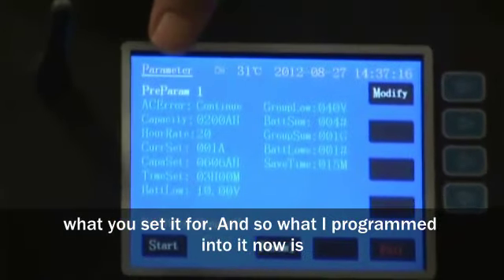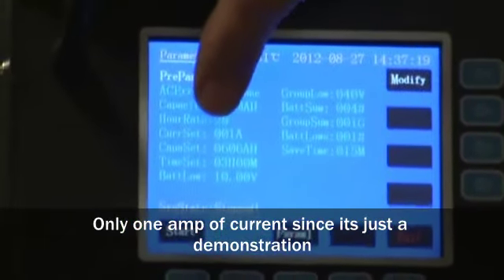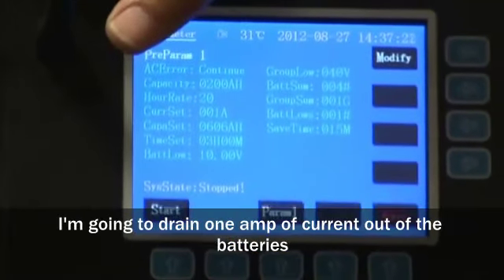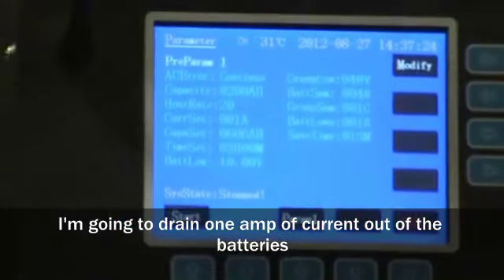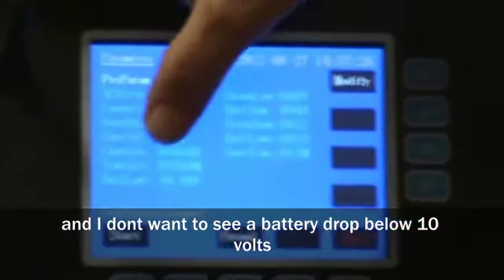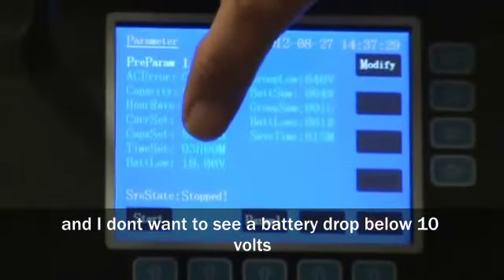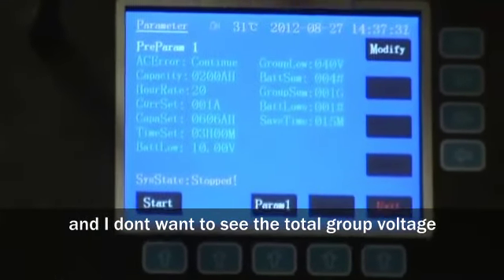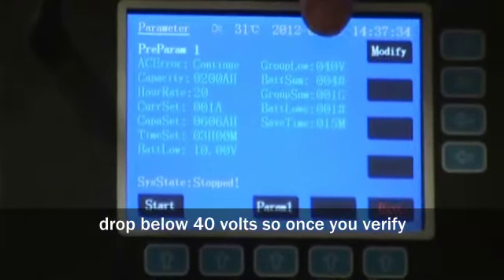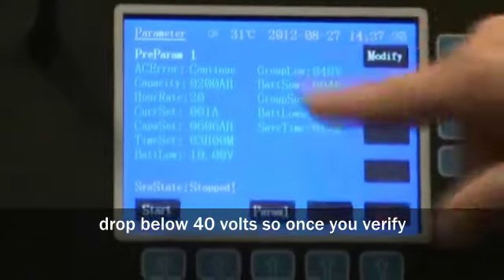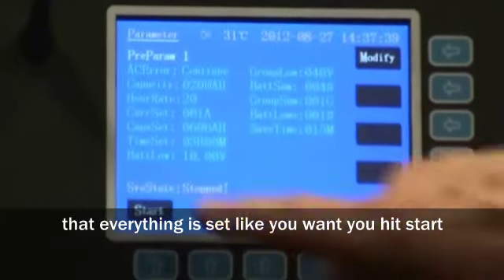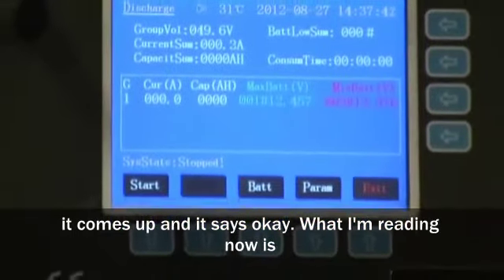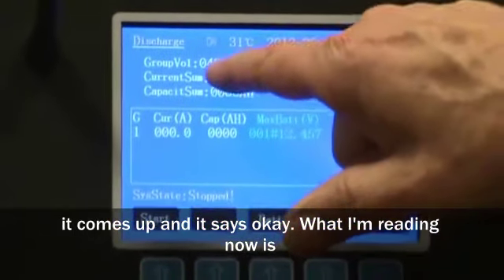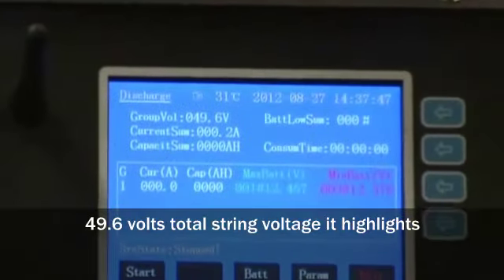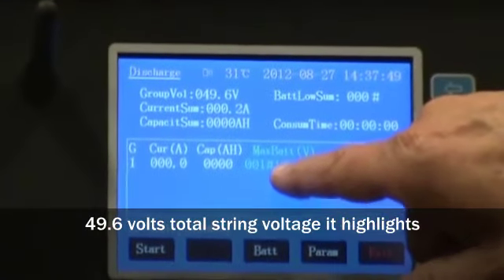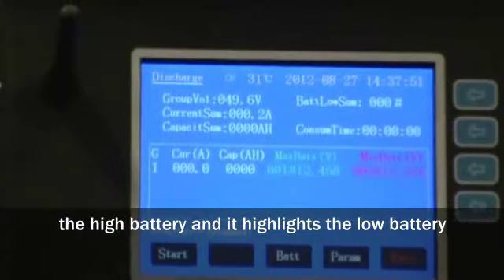And so what I've programmed it into now is only 1 amp of current, since this is just a demonstration. I'm going to drain 1 amp of current out of the battery, and I don't want to see a battery drop below 10 volts, and I don't want to see the whole total group voltage drop below 40 volts. So once you verify that everything is set like you want, you hit start. It comes up and says, okay, what I'm reading now is 49.6 volts total string voltage. It highlights the high battery and it highlights the low battery.